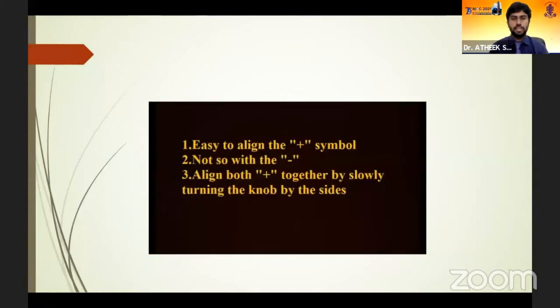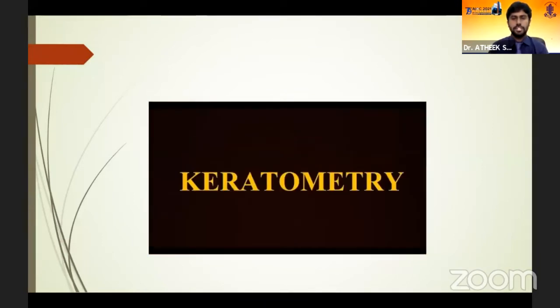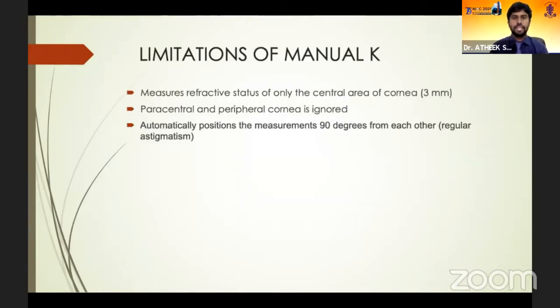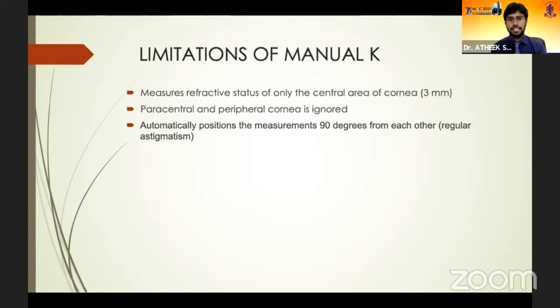Ensure that the patient is positioned well — these small things can give wrong values. The main limitations of manual keratometry include that it can only measure the central cornea; the peripheral and paracentral cornea are ignored. Another drawback is that this equipment assumes the cornea is always regular and symmetrical about 90 degrees apart. In cases with subtle skewing, this can be missed.